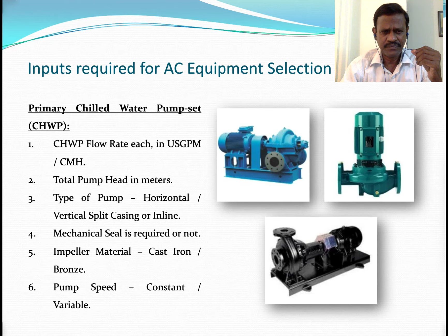Then pump speed. If you are going with a variable primary chilled water pumping system, then you have to give a VFD, variable frequency drive. Or if you are going for constant speed, constant primary chilled water pump sets, then you have to specify that. So you have to specify whether the pump speed is constant or variable. If it is variable, then you have to ask the vendor to supply the variable frequency drive panel also.